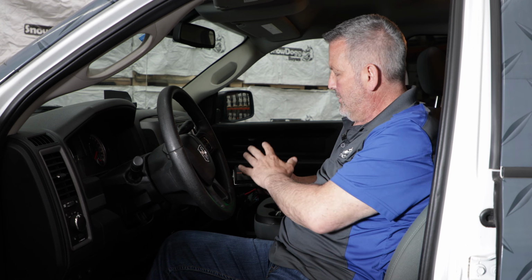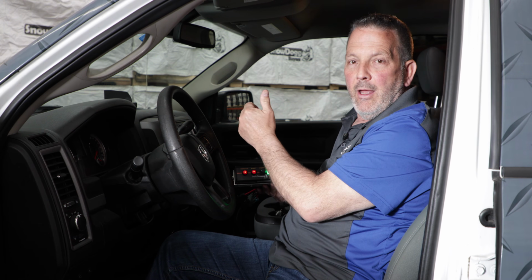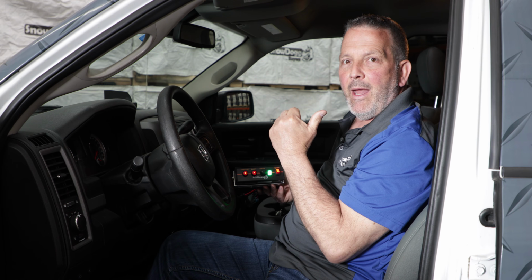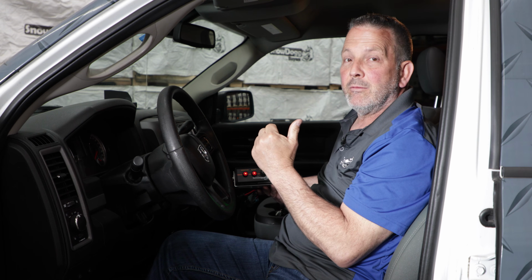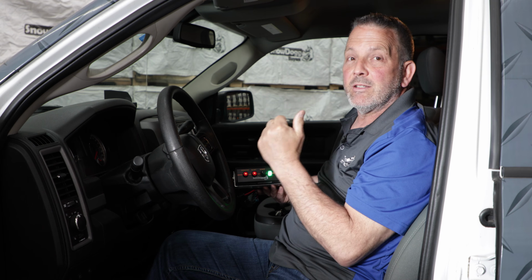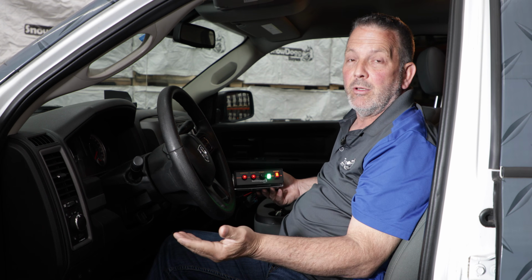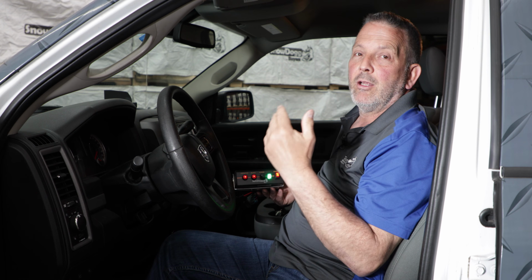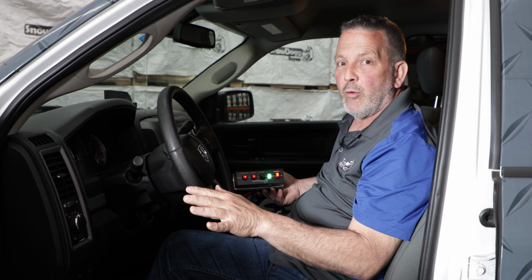In that situation, since I'm getting power here and it should be sending power to the back, but the motor's not running, we need to go check to see if the motor is actually operational. That's where we use a jump pack, jumping it with a 12 volt power source other than the controller, to see if it runs without the controller power.